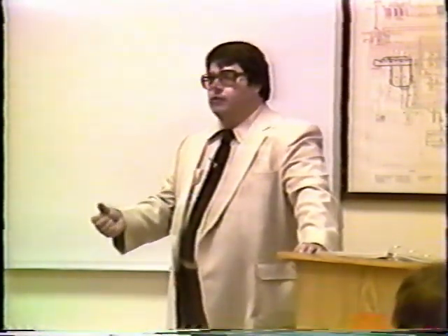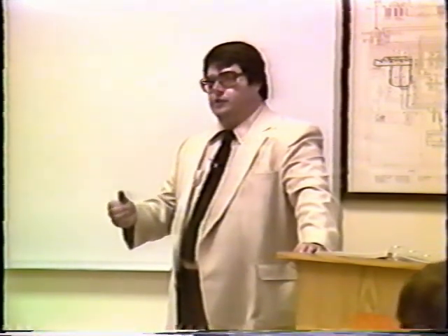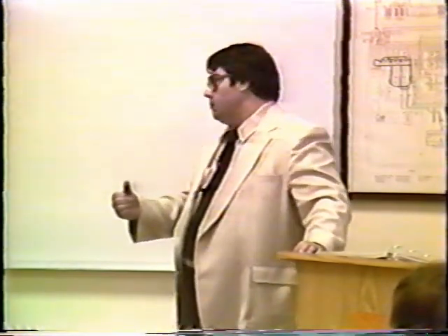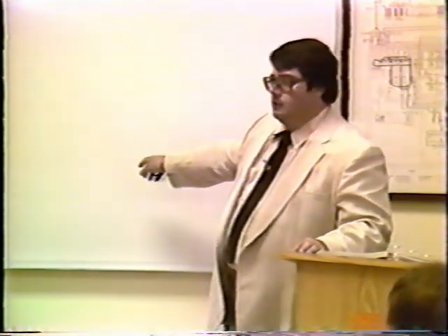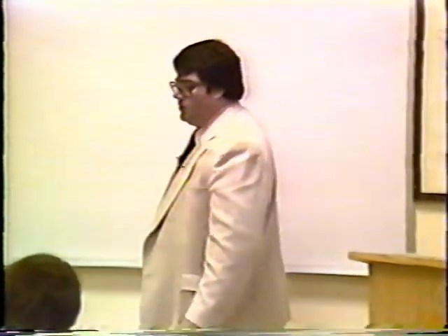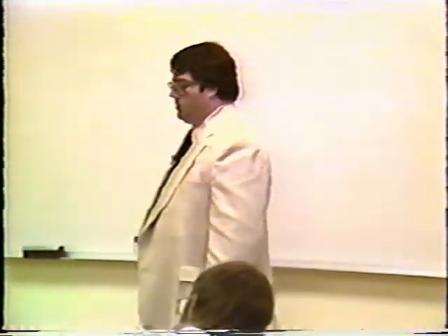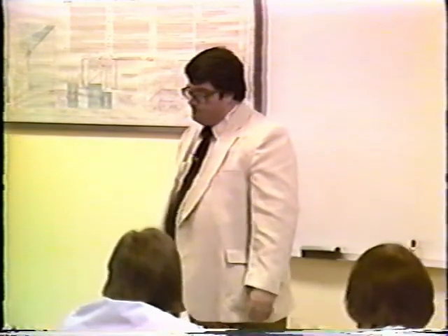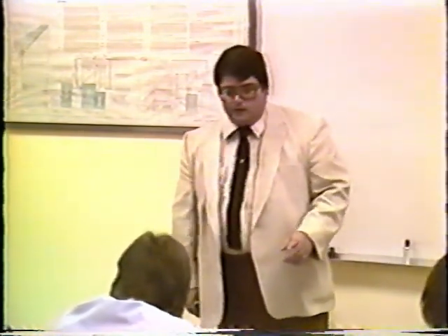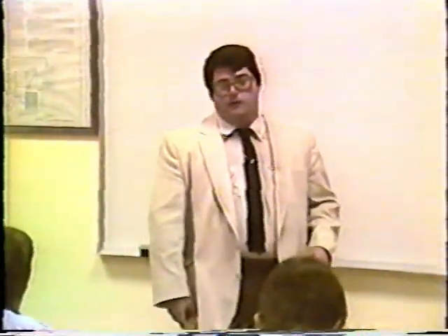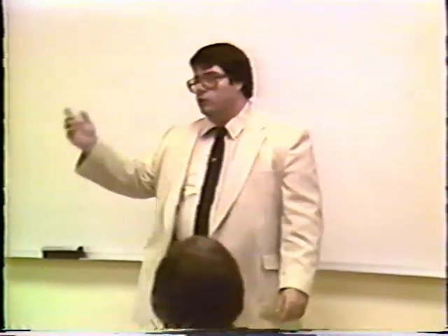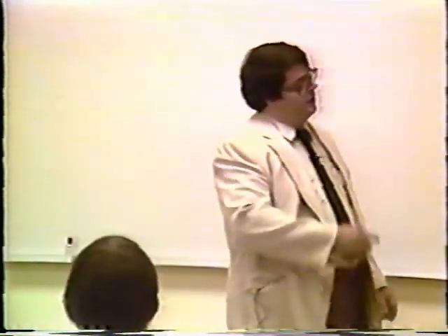Do all your monitors have that circuit in it that I talked about this morning that automatically takes into account source decay? As far as I know, only the density monitors, yeah. Only the density, not the level ones? I think it's actually Texas Nuclear, because they have sensitivity adjustments on them. I don't think it's done automatically. Okay, Ohmart, at least all the ones used at all the other facilities, do this automatically.